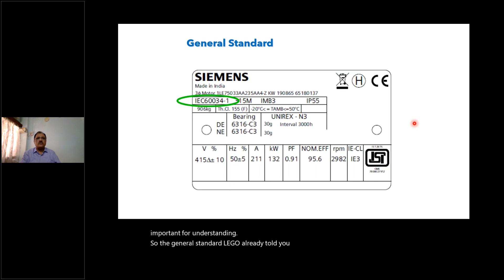So the general standard, like I already told you, is IS/IEC 60034-1. There are more than 20 standards governing different parts and different applications of motors, but I am limiting to about 5 or 6 here for your familiarity. IS/IEC 60034-1 is a general specification for induction motors in India. IS 12615:2018 is the latest revised standard for energy efficiency in our country. This covers from 0.12 kilowatt to 1000 kilowatt, 2-pole, 4-pole, 6-pole, and 8-pole.